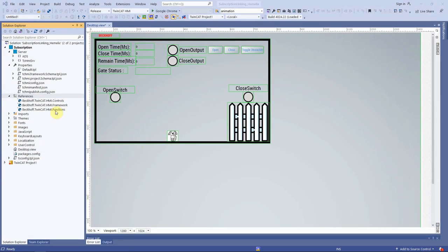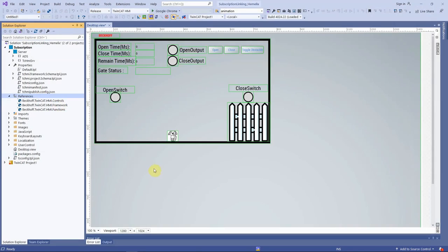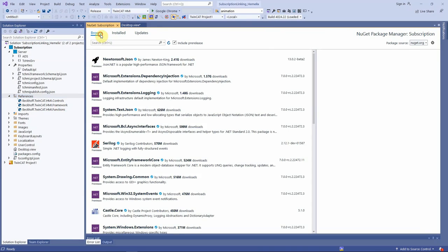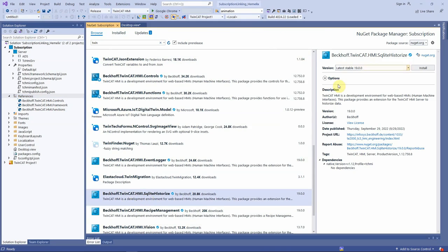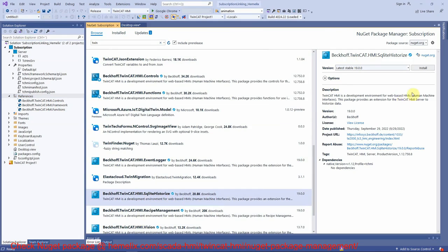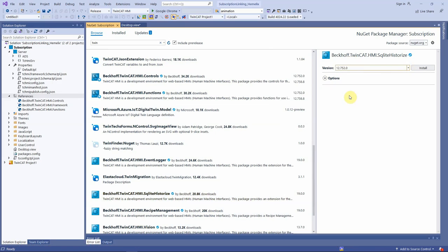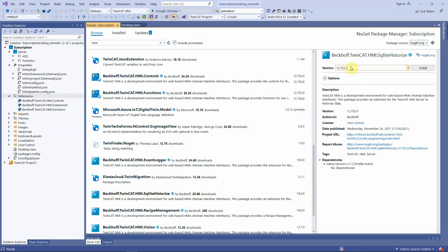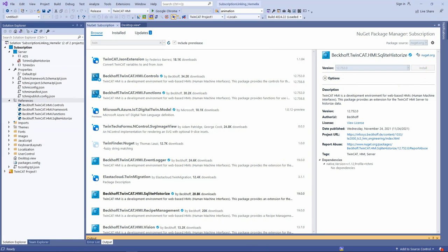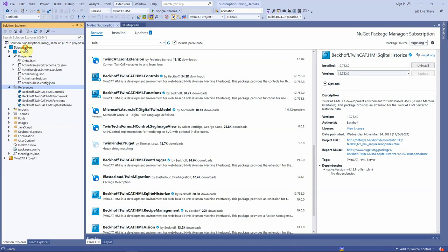Then to the reference folder of our solution, right click, Manage NuGet Package, and press on browse tab. Type TwinCAT in the search field. Find the SQLite Historize, select it, then select the right version from drop down list. We select 752.0, so this is our HMI engineering version. Press on the install button. Okay, now the extension is installed. This can be verified from the reference list. SQLite Historize has been added to the reference.